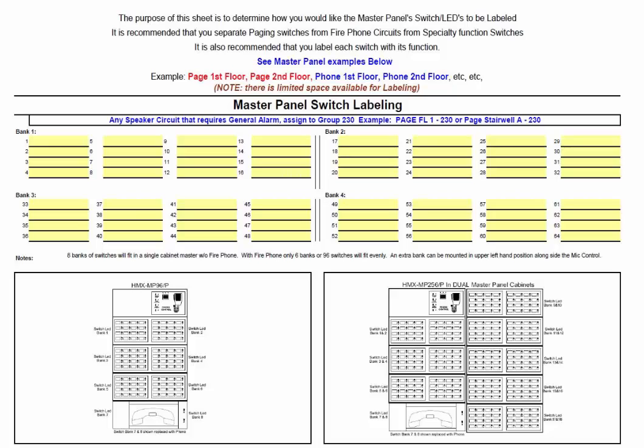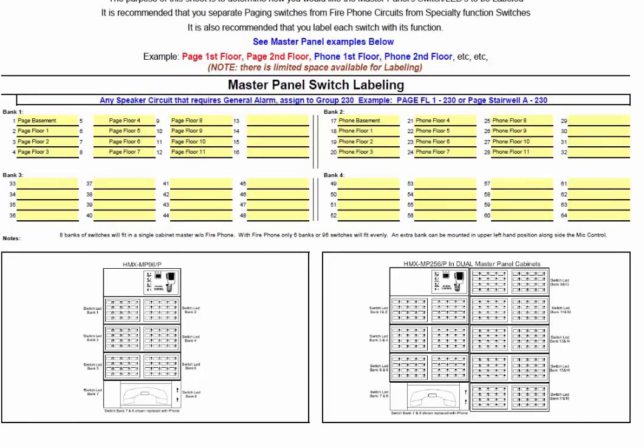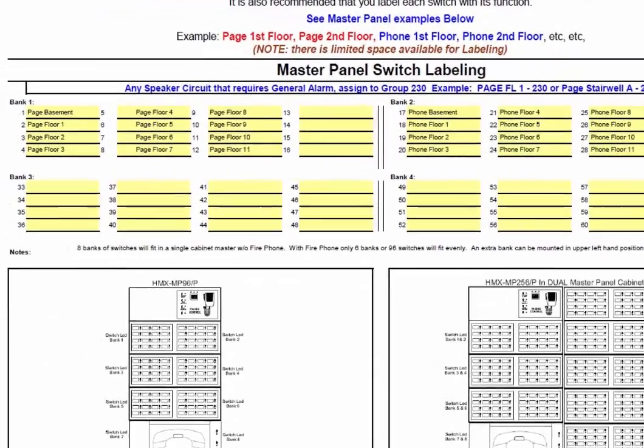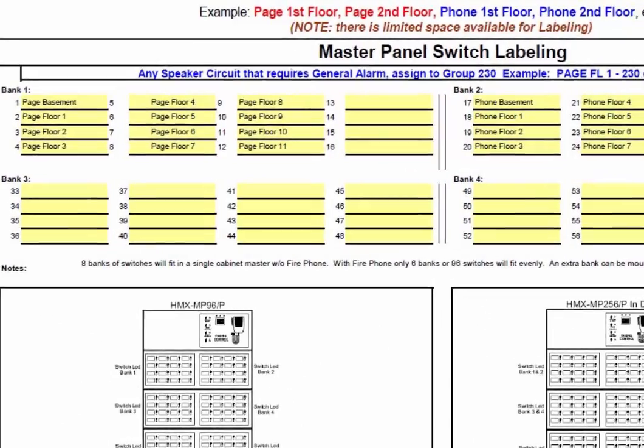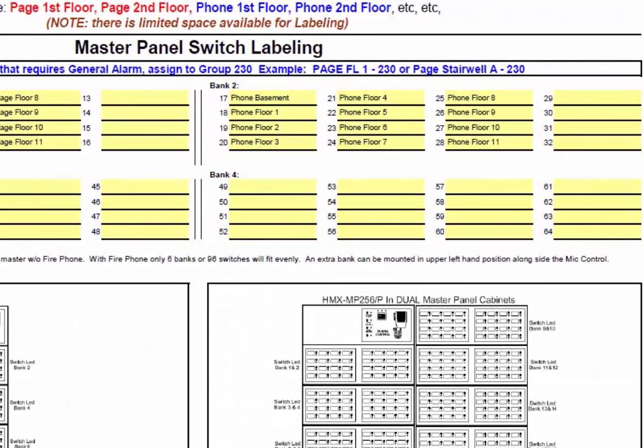Moving on to the tab labeled MP Switches, the purpose of this sheet is to determine how you would like the Master Panel Switches to be labeled. It is recommended that you separate Paging Switches from Fire Phone Circuits from Specialty Function Switches, and label each switch with its function. In the completed diagram, Bank 1 Switches are kept to Speaker Circuits, and Bank 2 Switches are used for Fire Fighter Phone Circuits. Most applications would include a switch assigned to either a single speaker circuit or a group of circuits to allow zoned or selective paging to specific floors or areas of a building. For fire phone systems, a switch is required for each fire phone circuit.